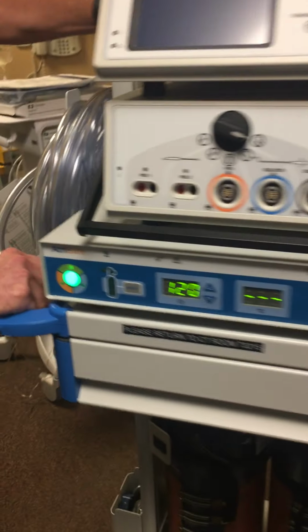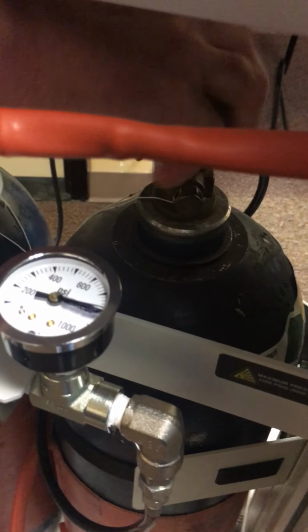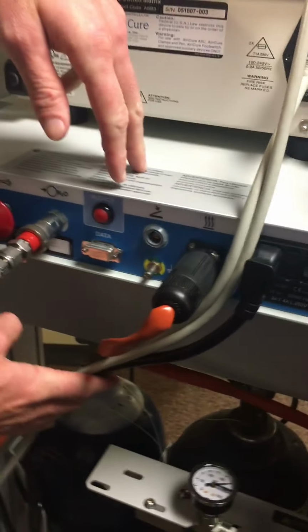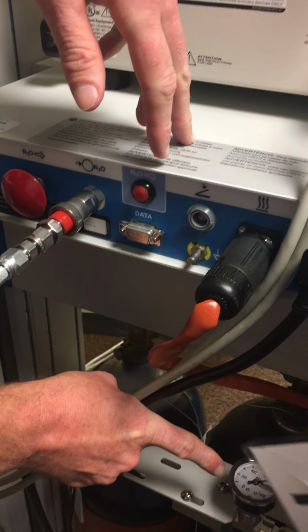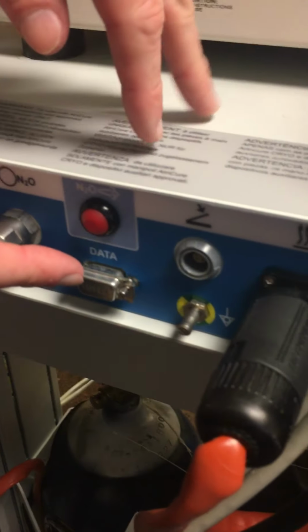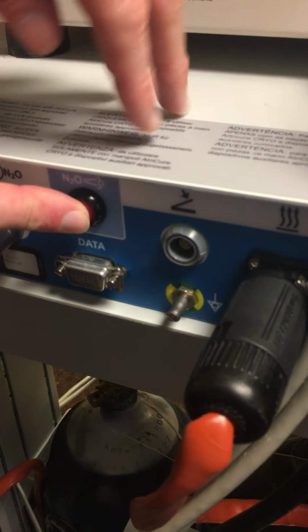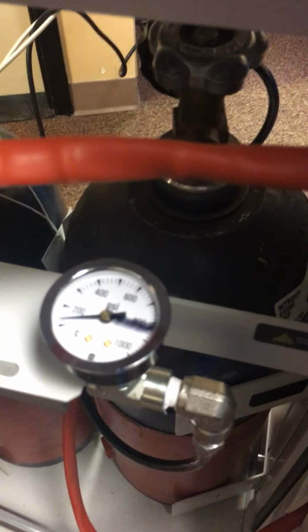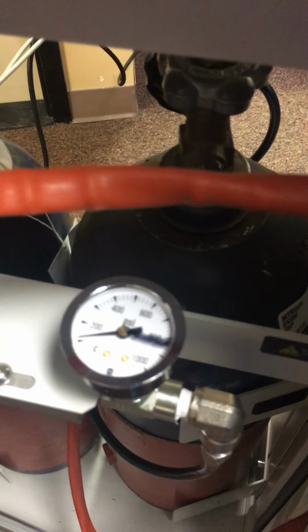Again, we want to turn the machine around, come to the back. First thing we want to do is close the nitrous tank. Again, righty-tighty to close. We are good there. Now we want to drain the line. So we still have pressure in the machine. We're at about 700. It's slowly going down because it's shut. So we want to expedite this process. So the machine's on, so I'm just pressing, and you can see here that the pressure gauge is going down. We're not quite at 0 yet.